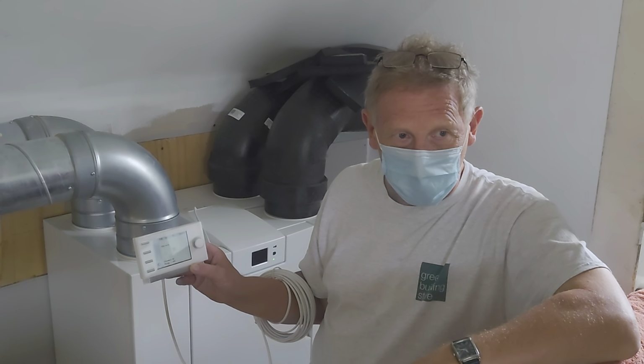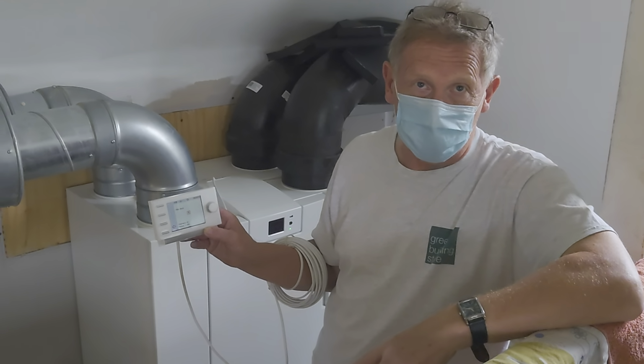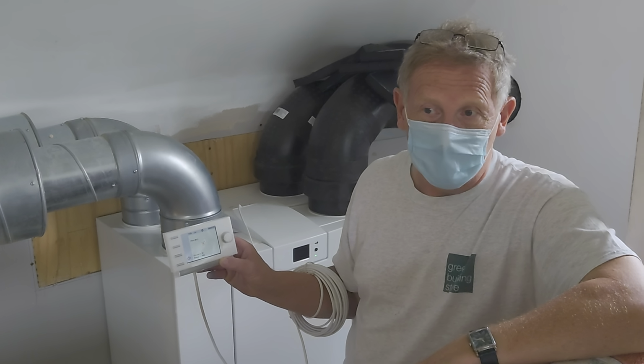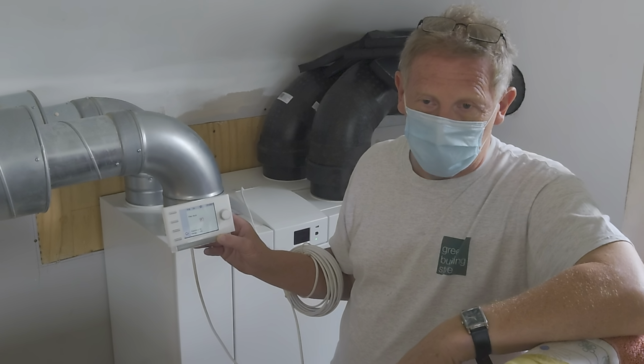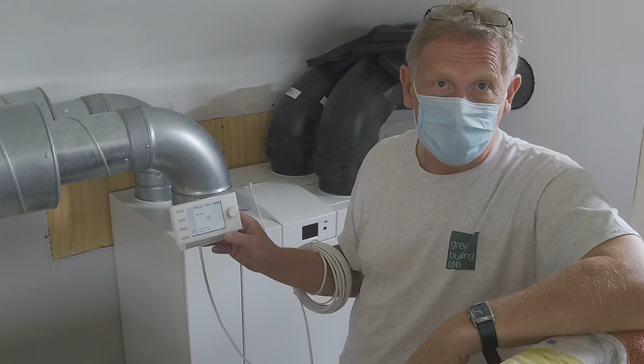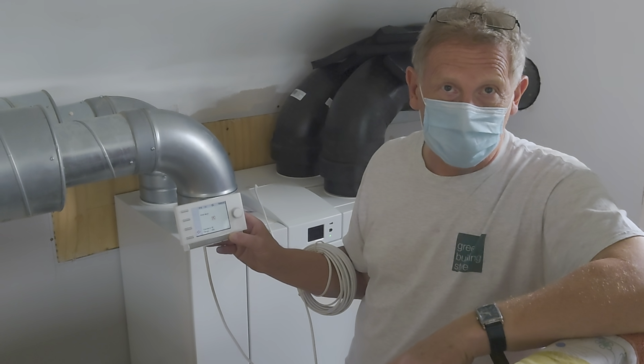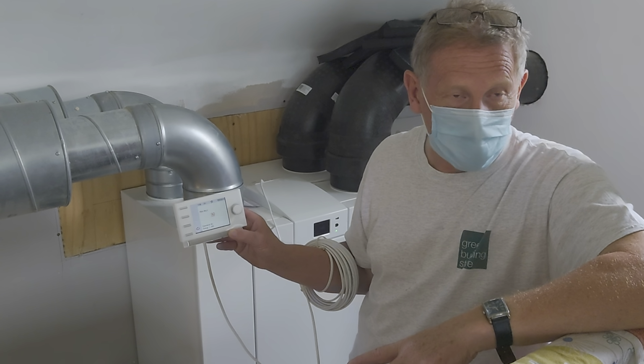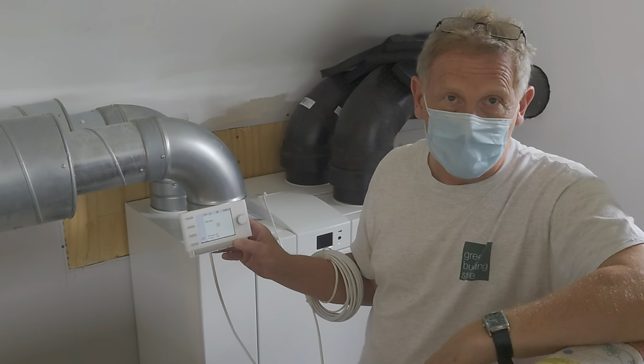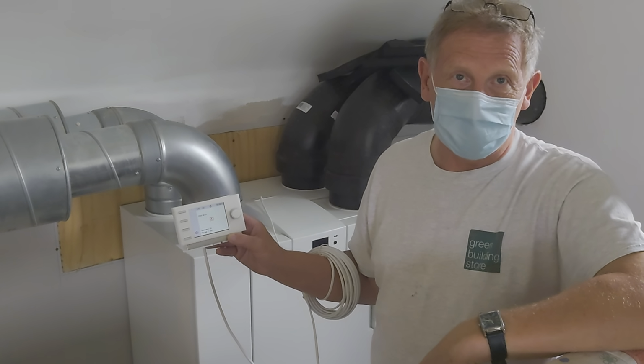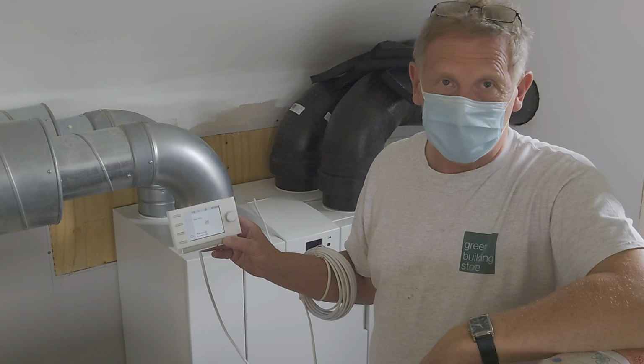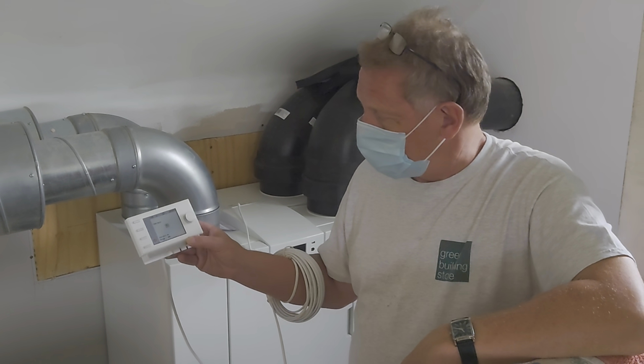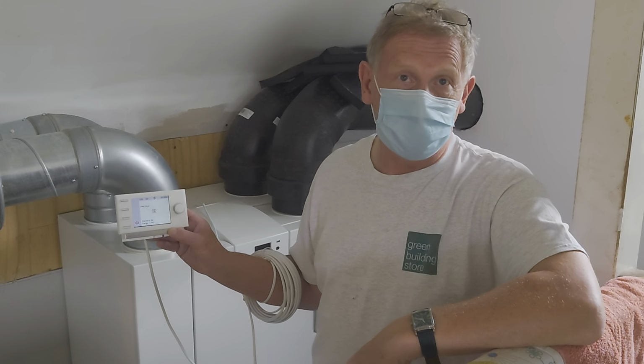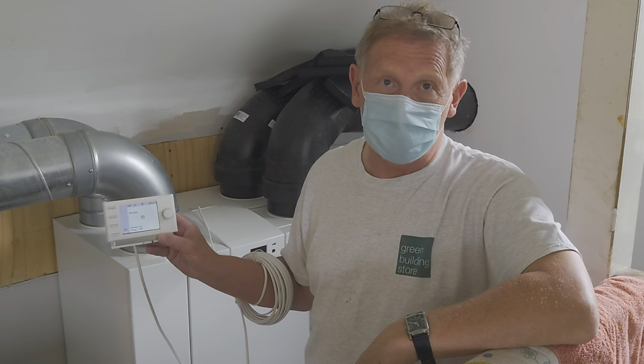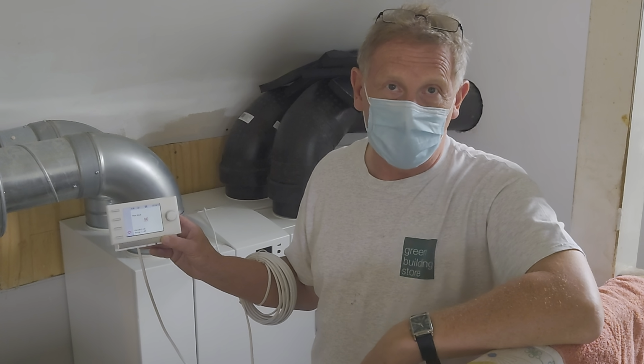The one on the extract side at the moment will just be dry building dust, which will come out fairly easily. Once everything's settled down and you've been showering and cooking, even that might get a little moist if someone's had a long shower, and the dust will stick to it and be harder to get out of the filter. So I think probably for the first year or so, leave it at 90. You don't have to change the filters, and you can always push them down and put them back in again.